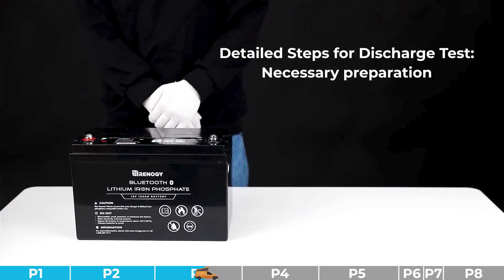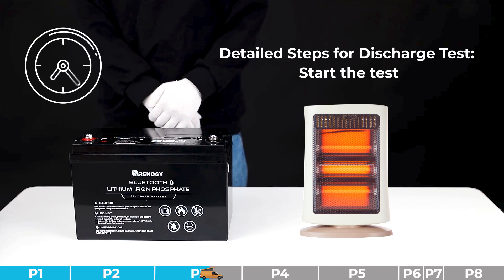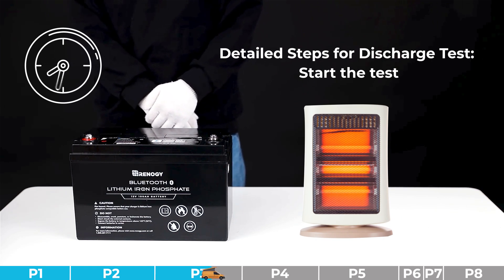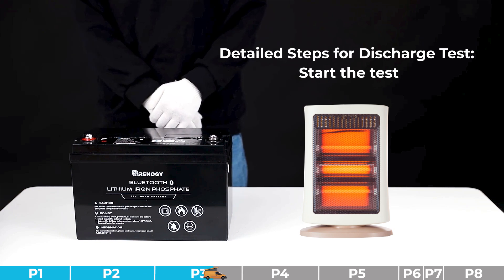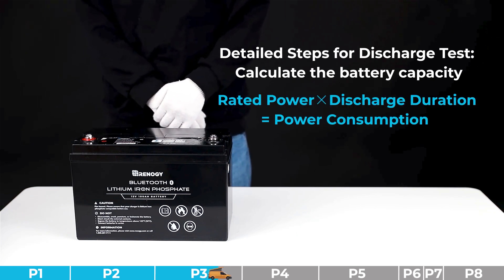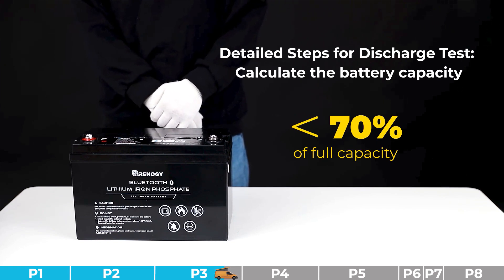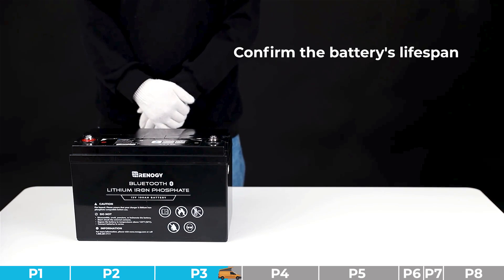Step one for the discharge test: find a resistive load with known power — for example, a heater. Use a fully charged battery to drive that load until the battery triggers BMS under voltage protection, at which point the battery will stop discharging. Record the continuous working time of the load. Calculate the actual battery capacity: rated power multiplied by discharge duration gives power consumption. If the power consumption is below 70% of full capacity, judge it as severe capacity degradation.